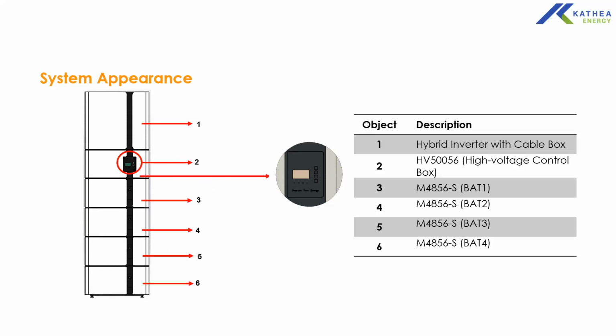Everything is the same. One good thing about the inverter, it supports unbalanced loads. So you can have one of your loads around 2 kilowatt, another load around 500 watts, another load around 800 thereabout. And it also restricts individual phase feed in. So you can actually control your feed in such that each phase is controlled separately. That's giving it the ability to supply unbalanced loads.